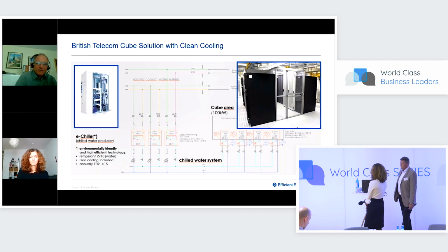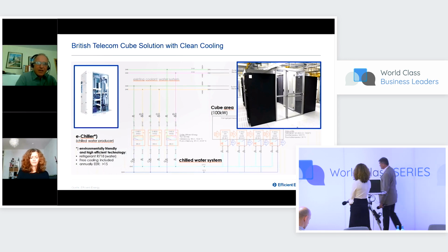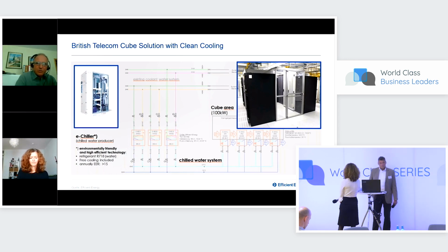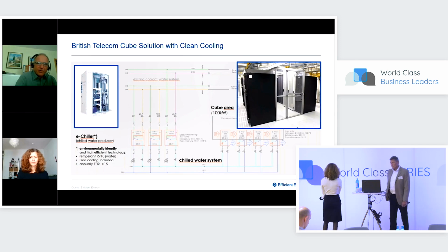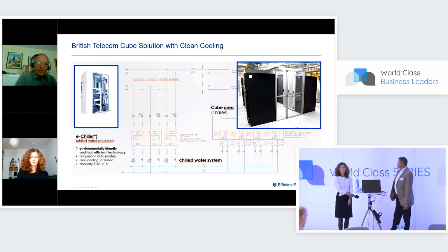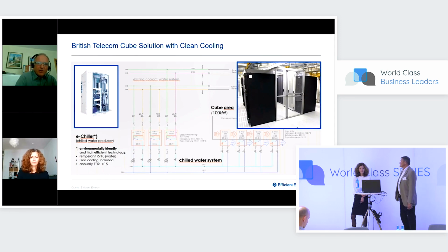For cooling, uniformly chilled water in-row cooling units are used, which are integrated into the rack rows in the cold and hot air installation. At required temperatures of 22 up to 25 degrees in the front of the rack, the very warm air emitted by the racks on the rear side is fed directly to the cooling units through a contained warm air aisle. This enables a very efficient cooling operation with relatively high media temperatures. As a result, the required chilled water supply temperature is relatively high too, at 18 up to 20 degrees.